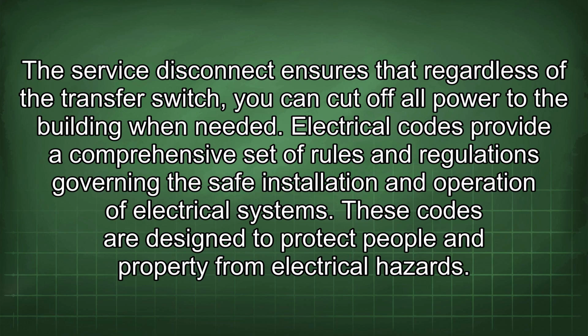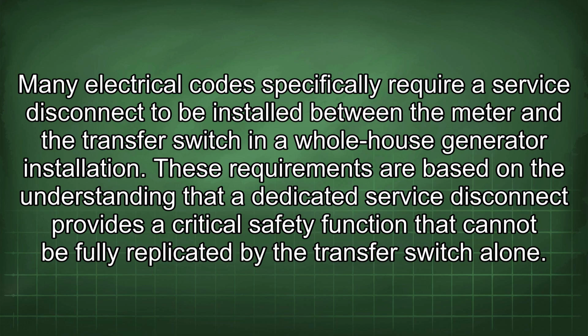Electrical codes provide a comprehensive set of rules and regulations governing the safe installation and operation of electrical systems. These codes are designed to protect people and property from electrical hazards. Many electrical codes specifically require a service disconnect to be installed between the meter and the transfer switch in a whole house generator installation. These requirements are based on the understanding that a dedicated service disconnect provides a critical safety function that cannot be fully replicated by the transfer switch alone.